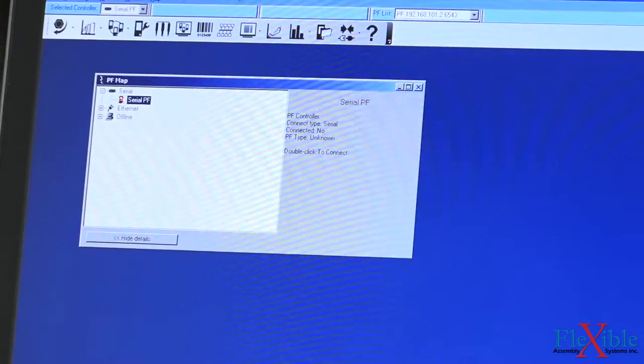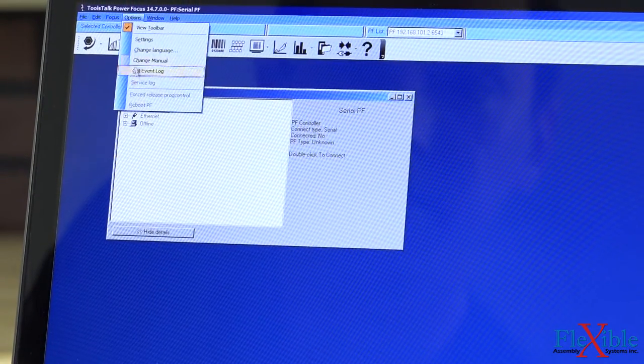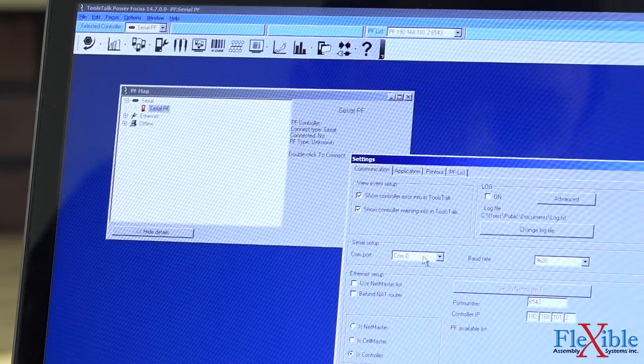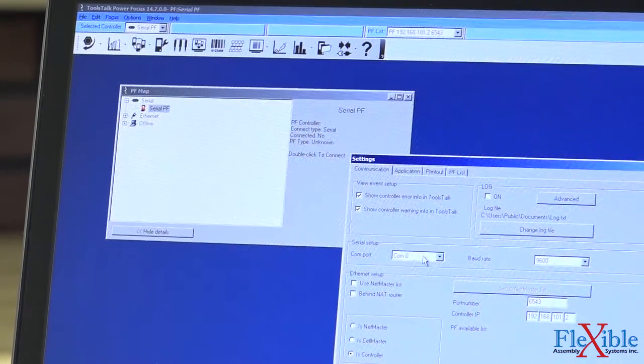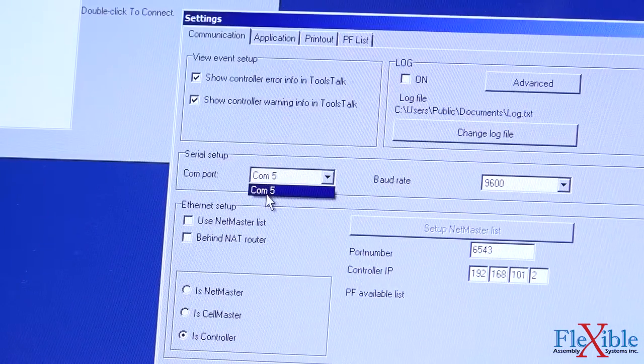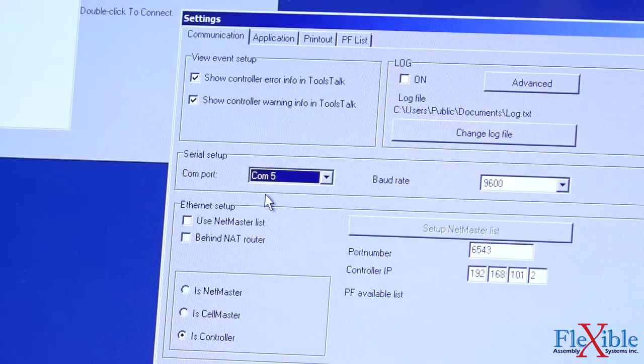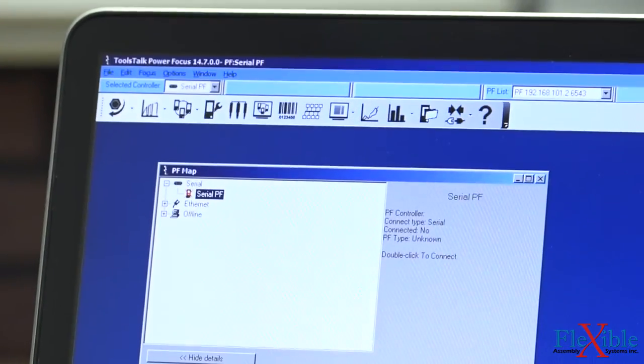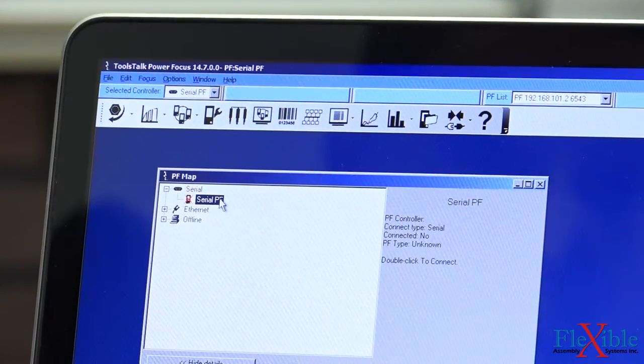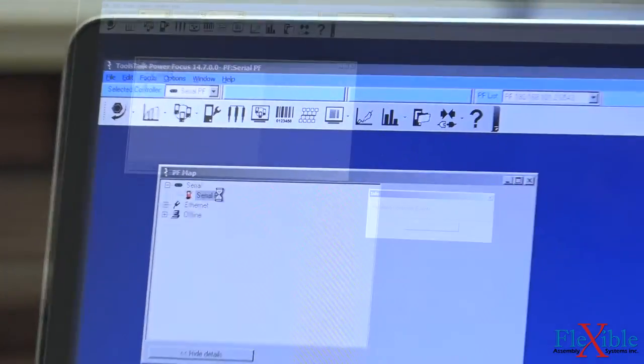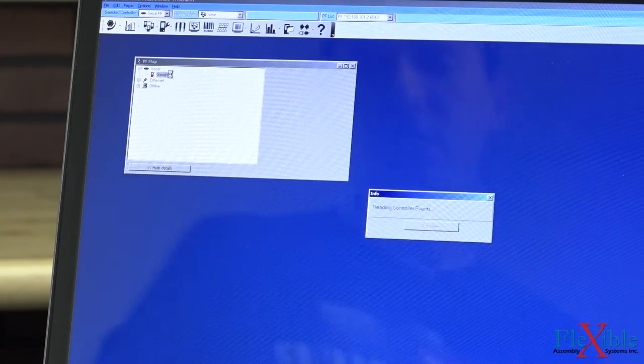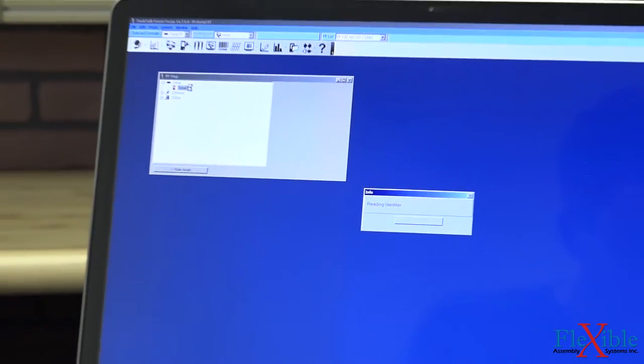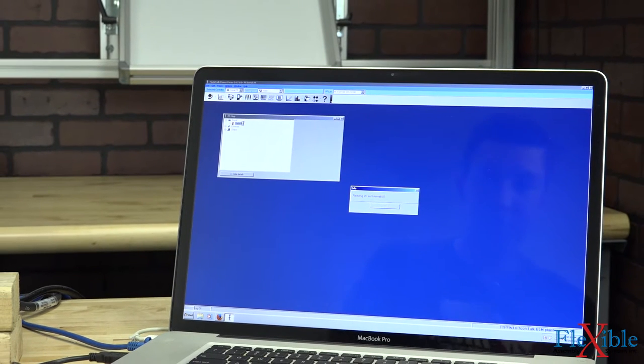We'll go up top to our Options menu. Go into Settings and then where it says Com Port it will default to Com Port 0. Once you click on it, it should only show you the options that are available. Since we only have one Com Port connected, we'll go ahead and hit Com Port 5. Then we hit OK. And back in our window over here we could double click on Serial PF and we should connect. This is a much easier way than connecting to Ethernet. However, you don't always have the option of having your laptop directly next to your controller and able to run a USB cable between the two of them.